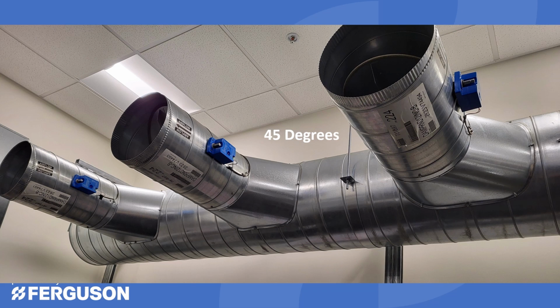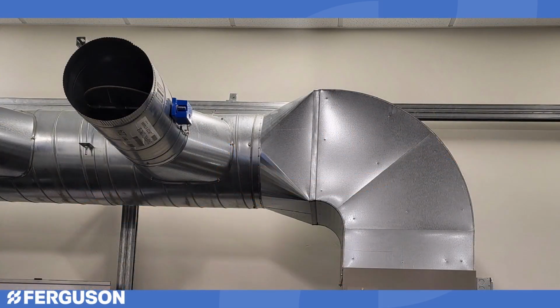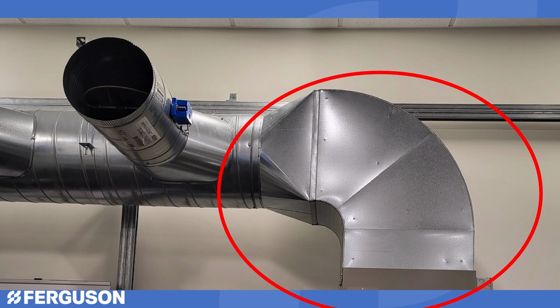So anytime you have takeoffs on a duct system, you should use 45-degree angles that direct the air into the ducts that you're taking off from the main ductwork. This will alleviate any turbulence or recirculation of air in the duct system. When coming off a furnace or an air handler, this type of fitting is preferred compared to a T-type fitting where you have right angles that air is going to hit and bounce off of and recirculate and turbulate. So when designing your ductwork coming off of a furnace or an air handler, use a long radius type duct system that will direct the air out of the furnace or air handler and into the main ductwork.